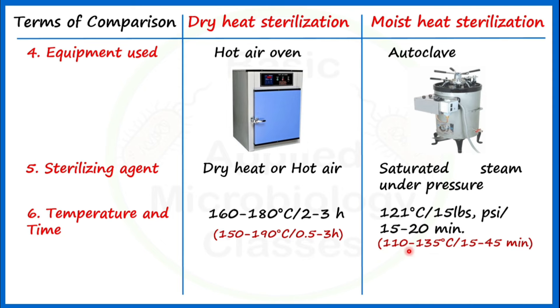In certain books, the temperature range for a hot air oven may be given as 150 to 190 degrees Celsius for 30 minutes to 3 hours, and for the autoclave as 110 to 135 degrees Celsius or more for 15 to 45 minutes. This variation is acceptable because it depends on the kind of material being sterilized. Generally, the first range is preferred and used in microbiology laboratories.